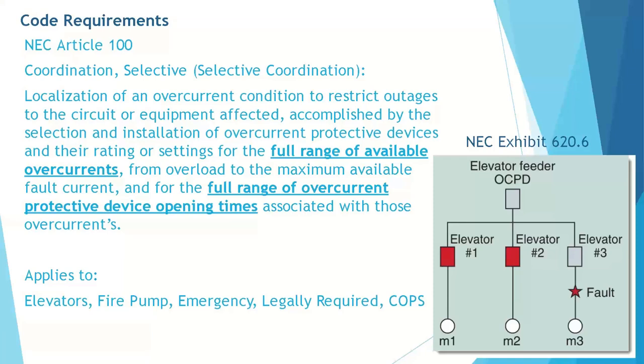For example, a feeder fault on elevator three will only open the breaker to elevator three and selective coordination will prevent other parallel elevator circuits from opening. Starting in article 100 with definitions, the intent of selective coordination is clearly defined to the localization of an overcurrent condition to restrict outages to circuits or equipment affected. This applies to many systems, elevators, fire pumps, emergency, legally required, and COPS.